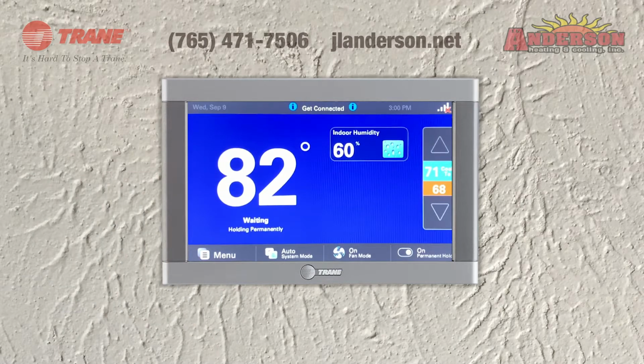If I try to get the two numbers closer than 3 degrees, it will actually push the other number down to compensate. I'll show you. And the reason for this is so that the heating mode and the cooling mode don't fight each other because they're trying to get too close to the same temperature.